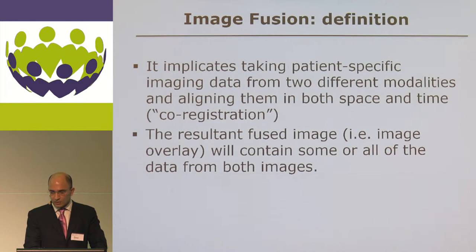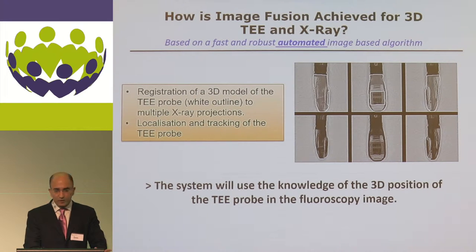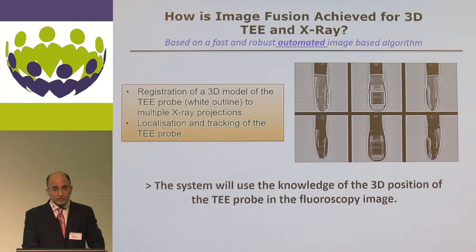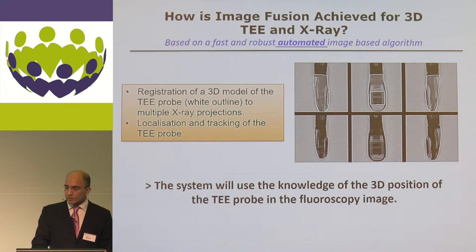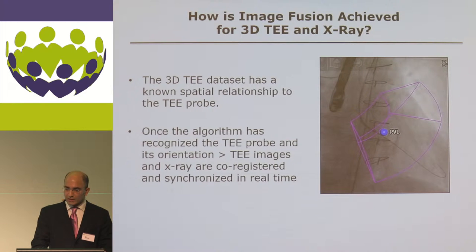The resultant fused image, or image overlay, will contain some or all of the data from both images. For 3D TEE and X-ray, the system is based on a fast and robust automated image-based algorithm. The algorithm uses prior registration of a 3D model of the TEE probe into multiple X-ray projections, allowing the system to localize and track the TEE probe. Since the 3D TEE dataset has a known spatial relationship to the probe, once the probe is tracked, TEE images and X-rays can be co-registered and synchronized in real-time.